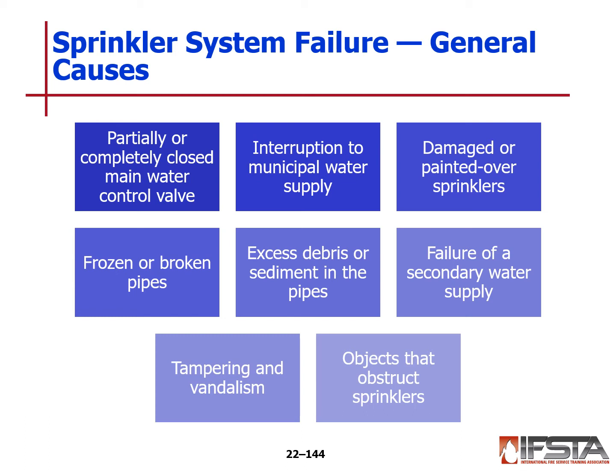Tampering and vandalism. One of the reasons why with our control valves and PIV valves that are on the outside, and wall indicator valves, we chain with breakaway locks is to reduce vandalism and tampering. And they may have tampering devices on them. So if somebody were to try to operate the valve, it will send a signal to the panel and cause the alarm to sound, which would summon the fire department. Objects that obstruct sprinklers as well. And the big thing that we see here is storage areas. What will happen is they will stack debris, material, merchandise, boxed merchandise stored and stacked too close to the head itself. And if it were to operate, it would basically block the pattern and would not be able to do its job effectively.